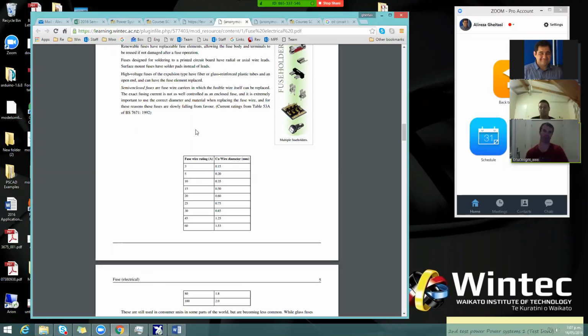That's something in protection you need to decide. Sometimes you need a backup for your fuse or your switch - your switch as the main protection and a fuse if that doesn't work, or the other way around. Or you have a sub-circuit protected with fuses or switches, and then protection of the higher circuit. That's a scenario you need to choose when rating your protection system.